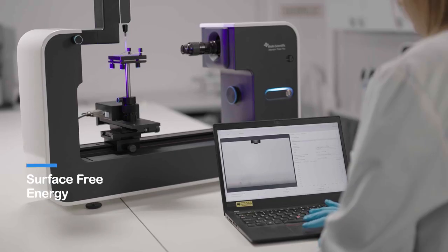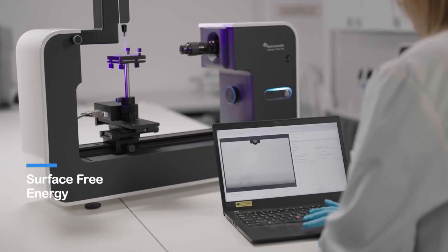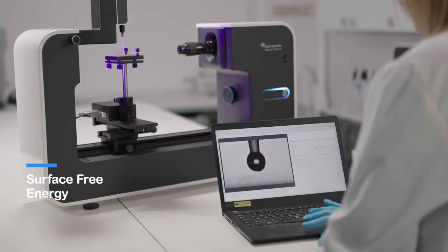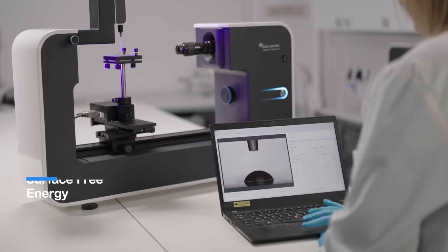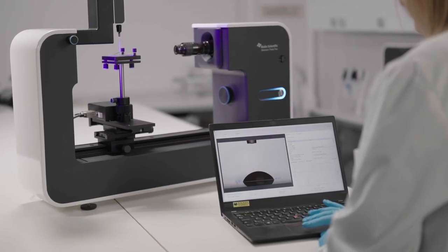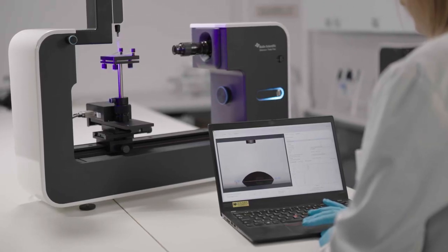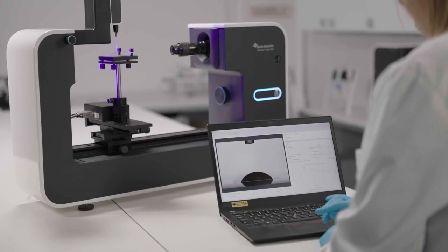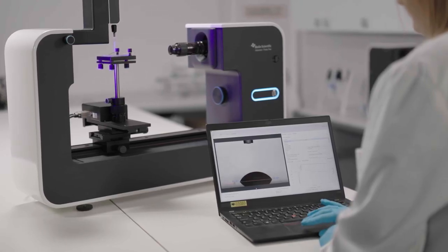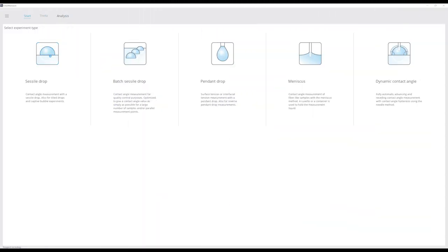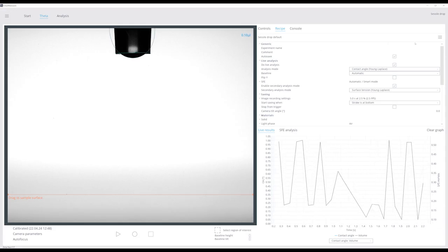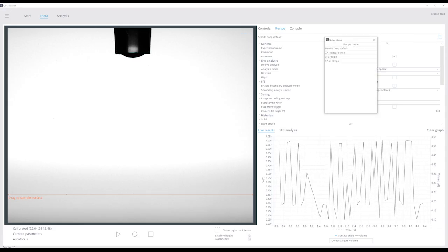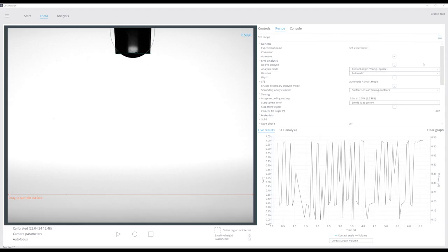Surface free energy is the property of the solid and it's calculated through contact angle measurement. To calculate surface free energy, you need to measure the contact angle with at least 2 different probe liquids, most commonly water and diiodomethane. Open the sessile drop measurement. It is possible to load a predefined recipe. Here a recipe for surface free energy measurements is selected.